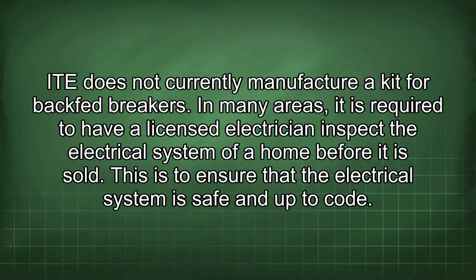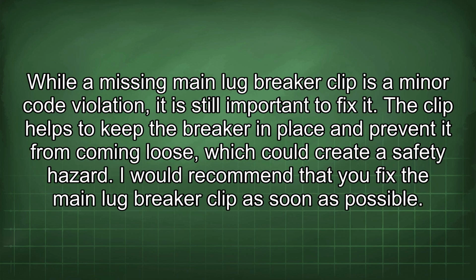ITE does not currently manufacture a kit for backfed breakers. In many areas, it is required to have a licensed electrician inspect the electrical system of a home before it is sold. This is to ensure that the electrical system is safe and up to code. While a missing main lug breaker clip is a minor code violation, it is still important to fix it. The clip helps to keep the breaker in place and prevent it from coming loose, which could create a safety hazard. I would recommend that you fix the main lug breaker clip as soon as possible.